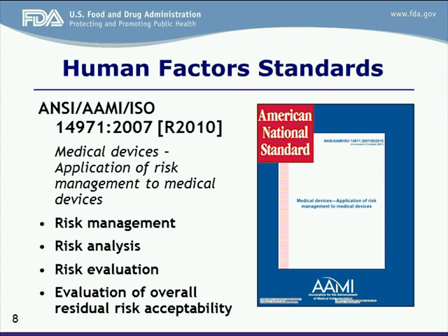Also, while not a usability standard, 14971, the risk management standard, is integral to everything we'll be discussing today, because usability engineering and risk management activities are interwoven throughout product development and product lifecycle.